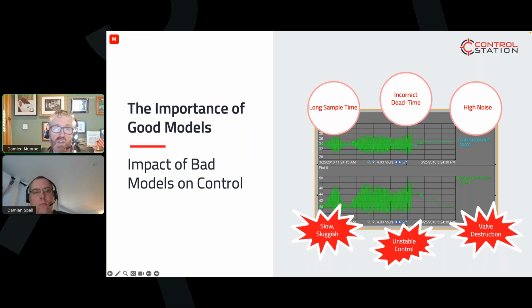Every vendor is going to give a warranty or rating on those pieces of equipment, maybe 1 million cycles, which is a huge reliability. But if we use the data incorrectly and put in tuning parameters or over-aggressively control, it's going to wear out those components. It may not happen today or tomorrow, but you're shortening the usable time of that valve, that system, and increasing your maintenance requirements to do those kinds of things.